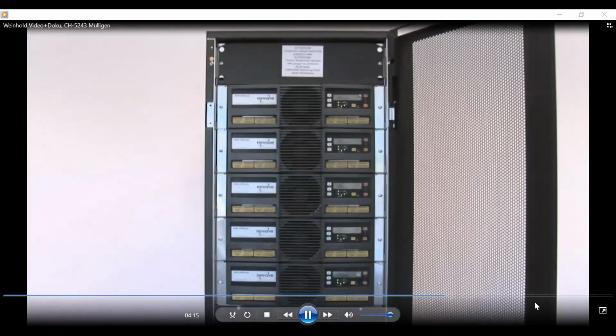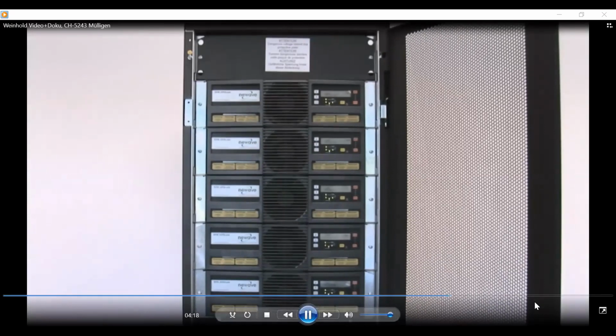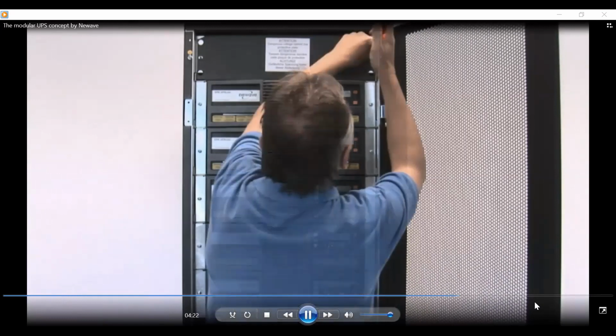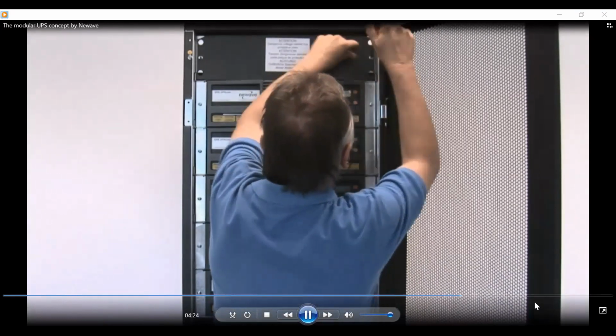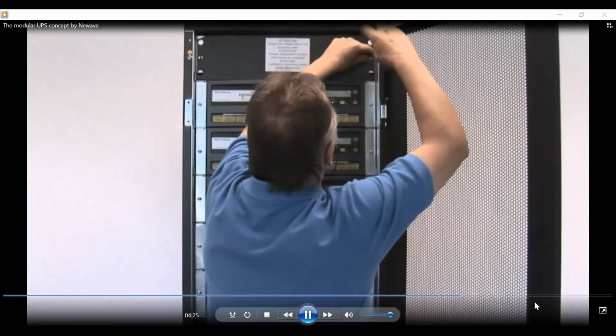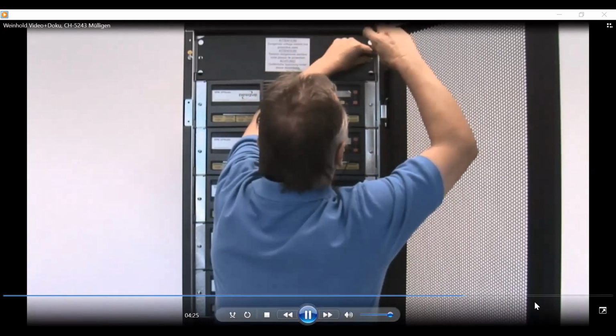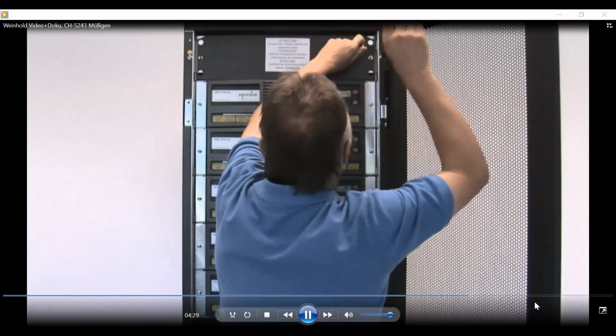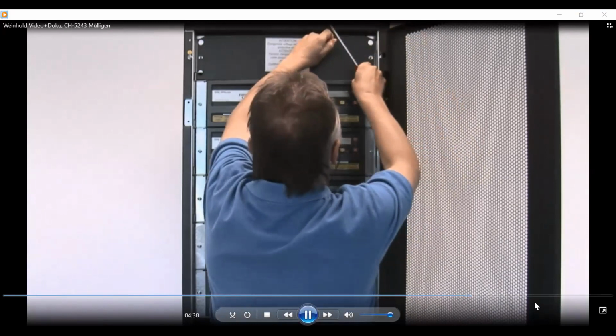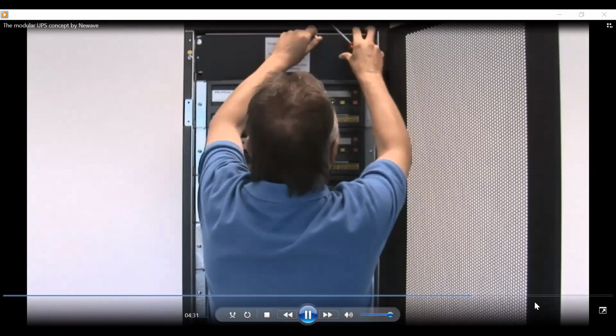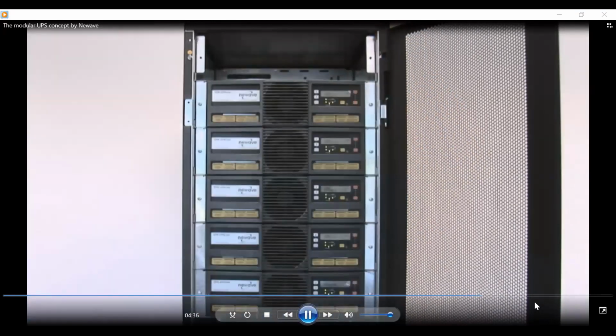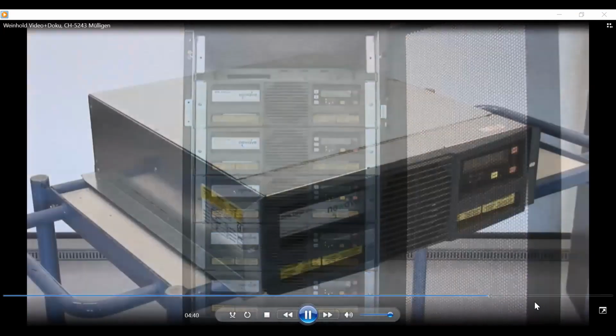This picture shows an example of a typical vertically scalable UPS system. In this example, a UPS system cabinet capable of housing up to 6 UPS modules initially contains 5 UPS modules. The 6th slot is left empty. If the critical load increases above the installed UPS power, then an additional UPS module could be added to the cabinet.